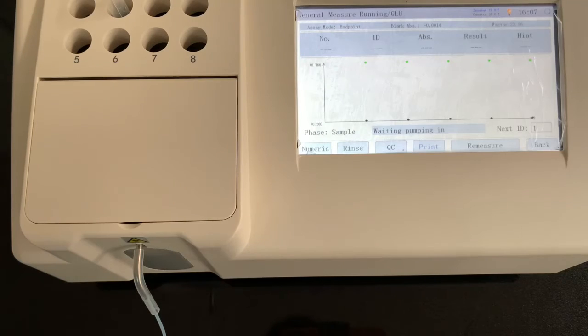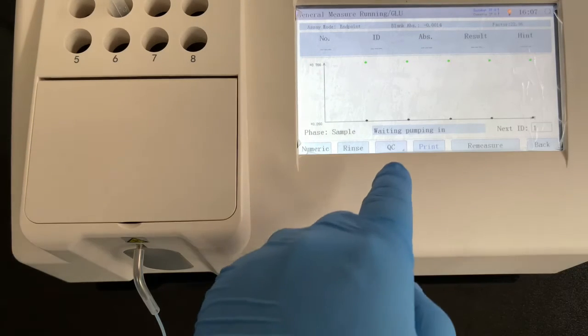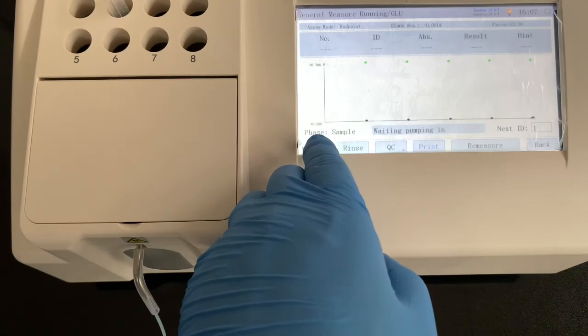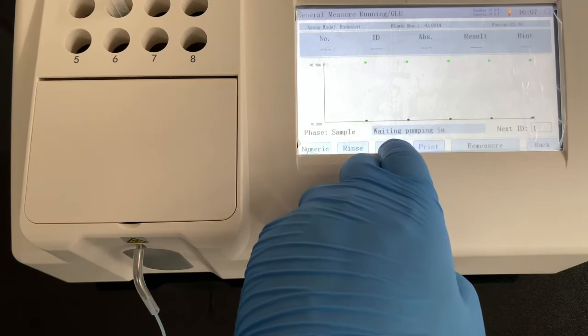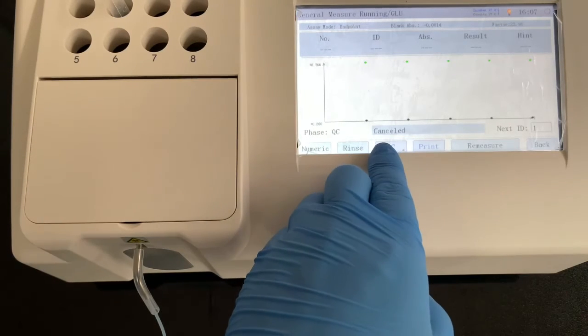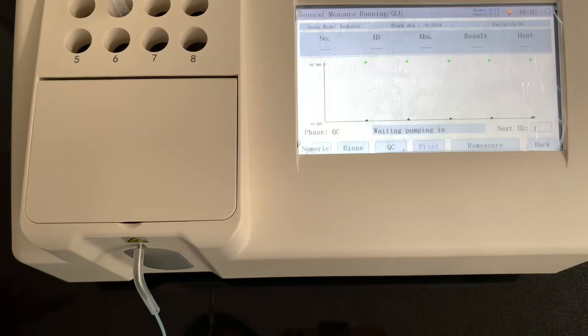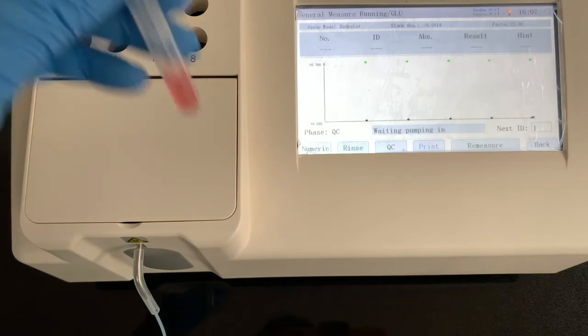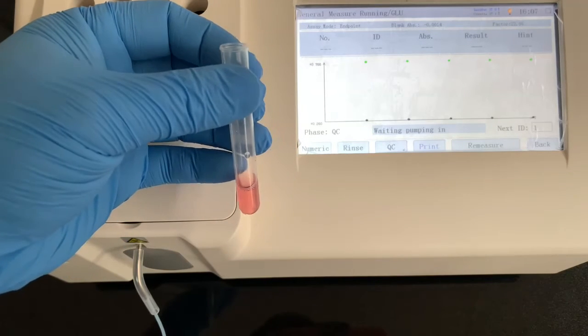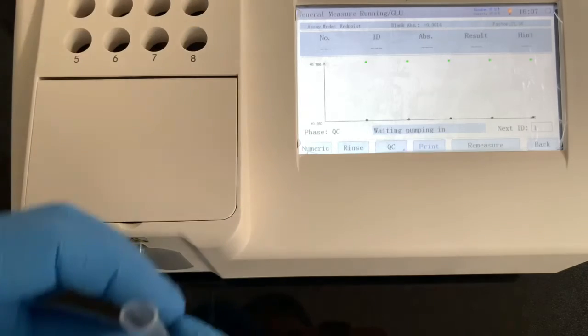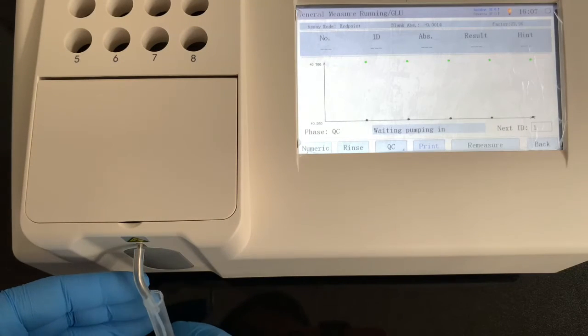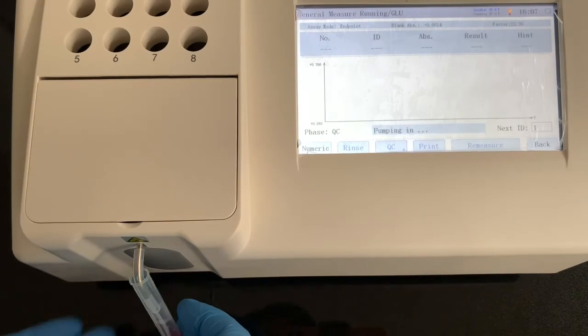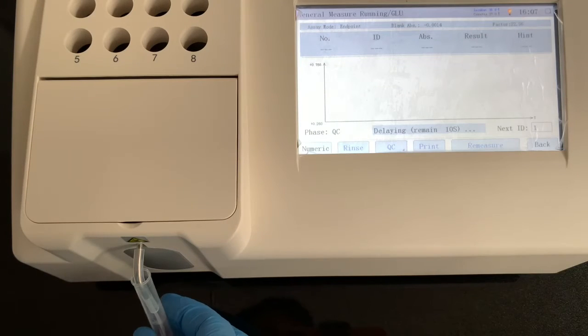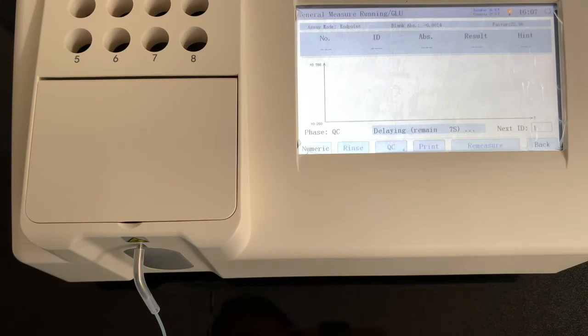Next, we run QC. Before we test QC, we have to change the phase to QC by tapping the QC button. This is our QC solution. It is also prepared. After delay, analyzer will test QC solution.